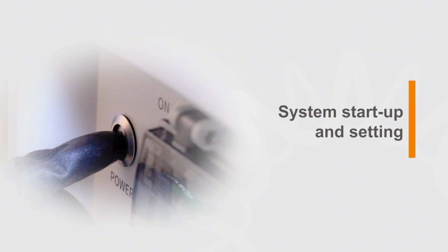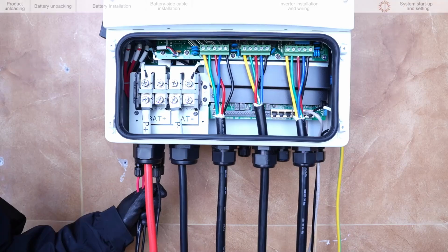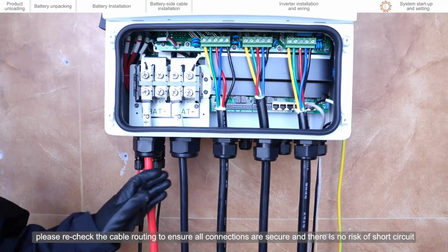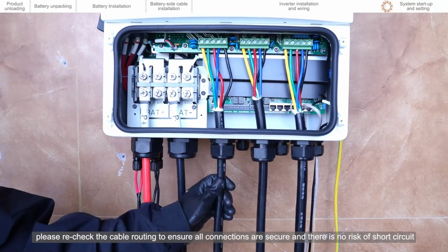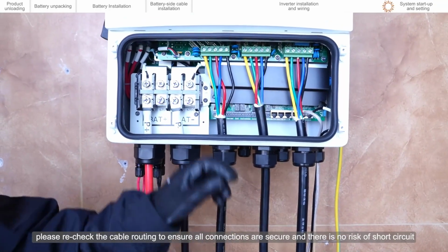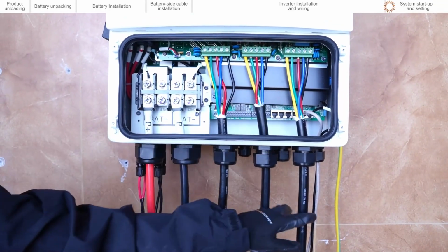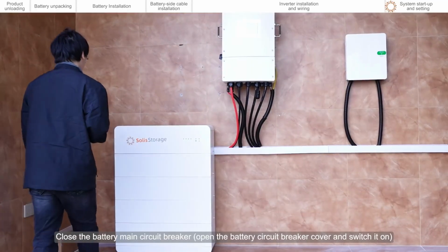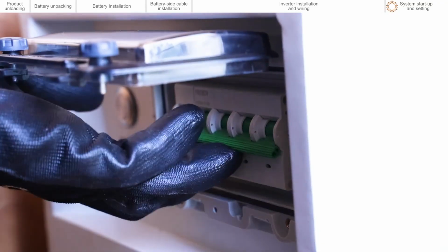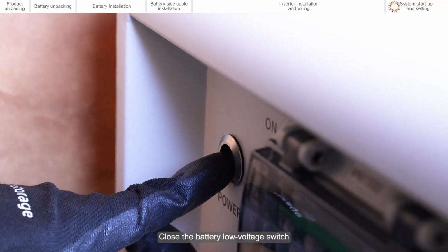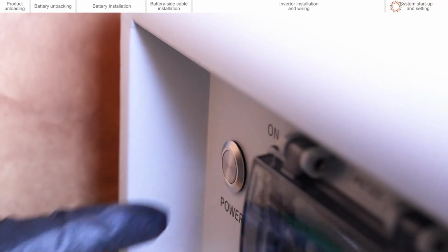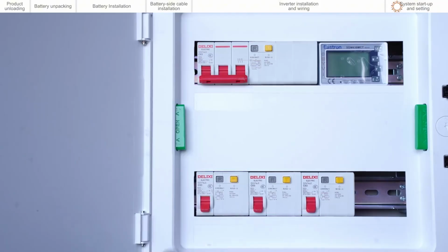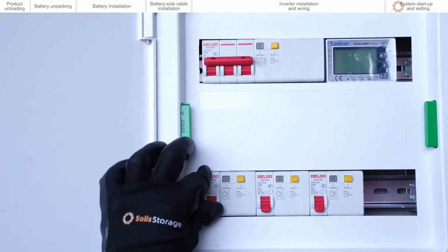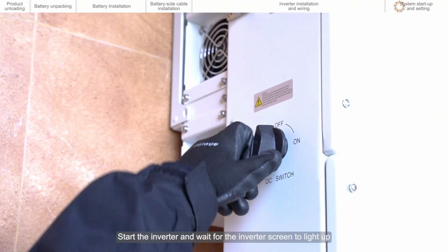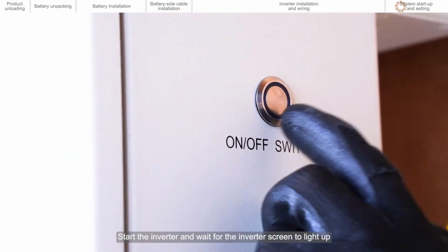System startup and setting. Before starting the system, please recheck the cable routing to ensure all connections are secure and there is no risk of short circuit. Close the battery main circuit breaker. Close the battery low voltage switch. Turn on the distribution switch. Start the inverter and wait for the inverter screen to light up.